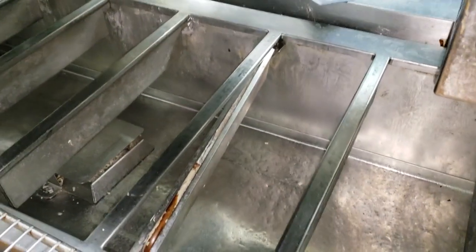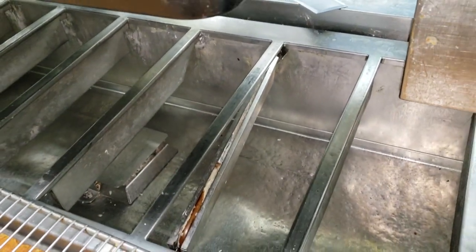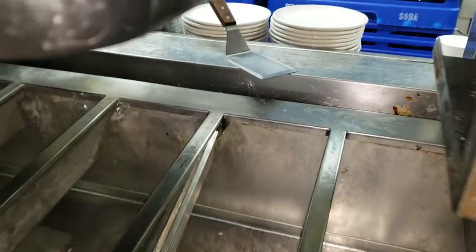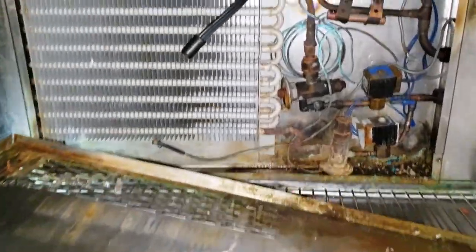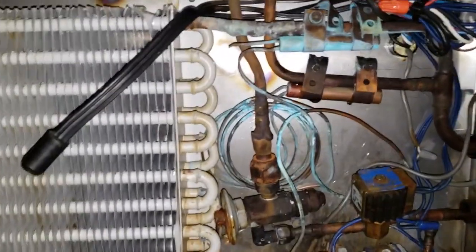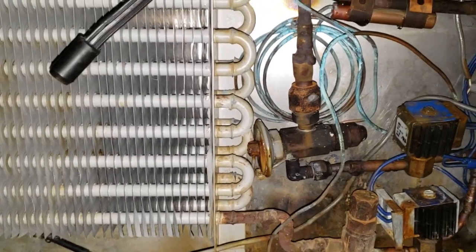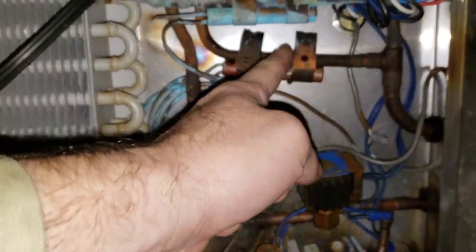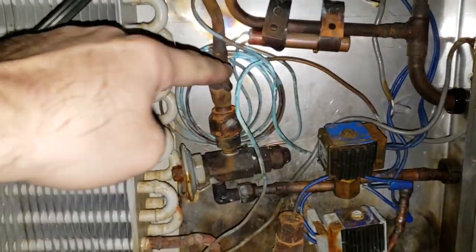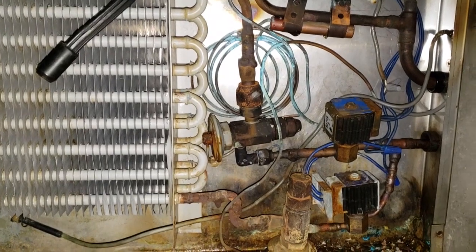I'm going to talk to the customer and see if they want me to do a temporary fix. They have a guy that will come in and fix this — he'll cut the top of this and re-weld it when he's done. Look how they fit a flared valve in there. What the customer wants me to do is temporarily isolate the top. We're going to cut right here and right here, pinch it off, and weld it shut so that way it doesn't leak anymore.